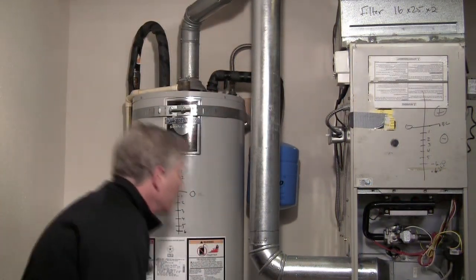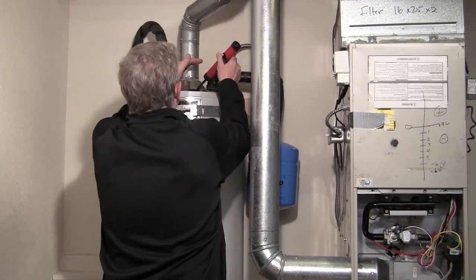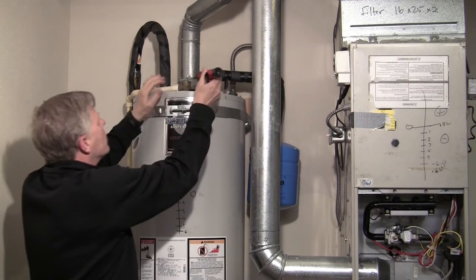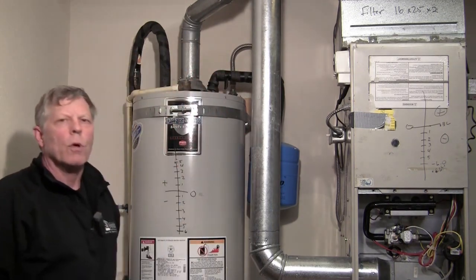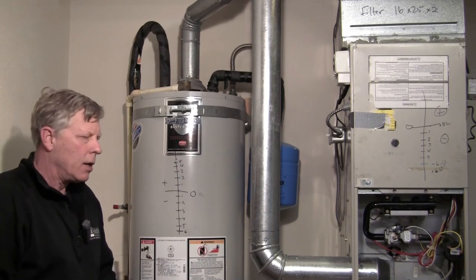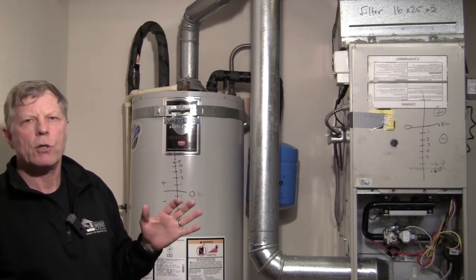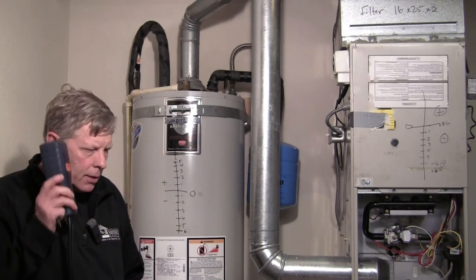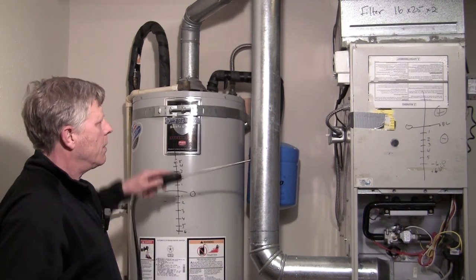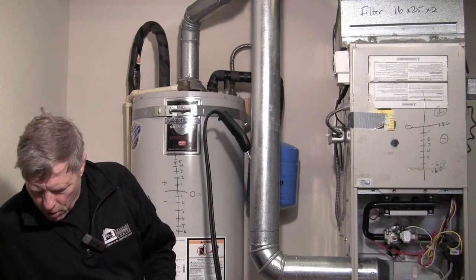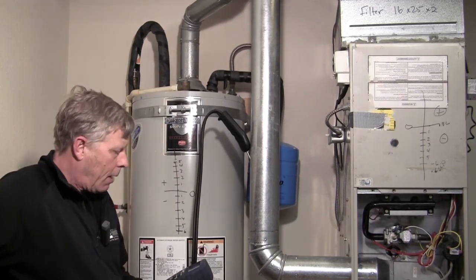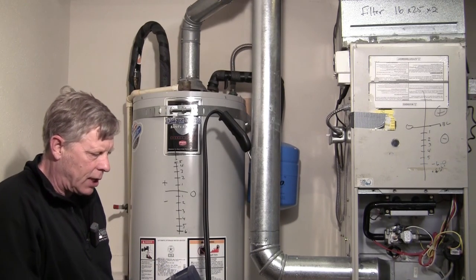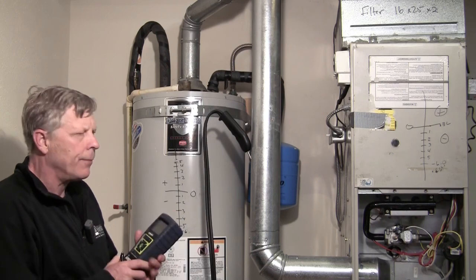Okay, it's been 2 minutes. We're going to check for spillage up here, and it's still spilling here. And it looks like we're spilling out of the chimney tube. So the furnace fails spillage. Now we'll wait another 3 minutes to get our CO measurement. I'm set up on CO air free. It's been 5 minutes. My ambient CO is still 0. And we're going to go ahead and get a reading on the air efficiency and also the air free CO.